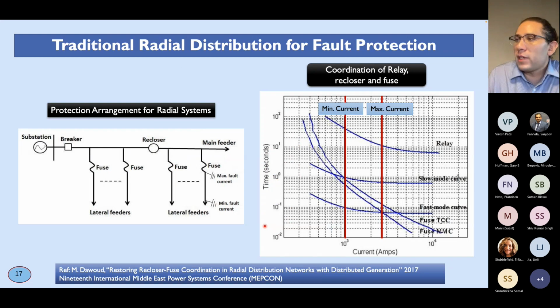This figure is showing how a traditional relay operation works. We do have a substation here. We have different items: the breaker, the recloser, and the fuse. The fuse is the one responsible for the permanent faults downstream of the line. The recloser is the one that actually operates first. It operates in a fast mode, as we can see in the figure on the right-hand side, between the red lines. The fast mode is fast enough to give the fault a chance to self-clear, in case it was a branch or a tree.